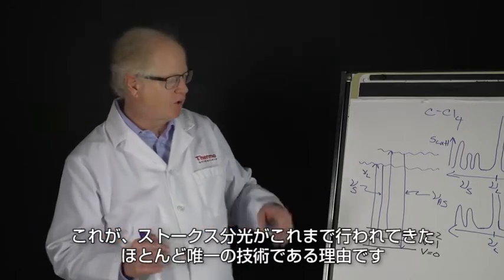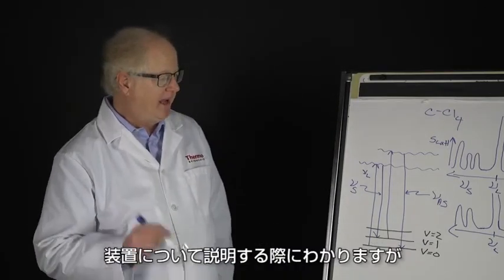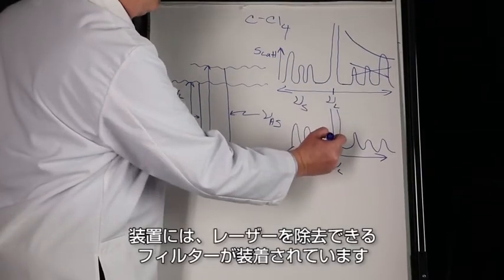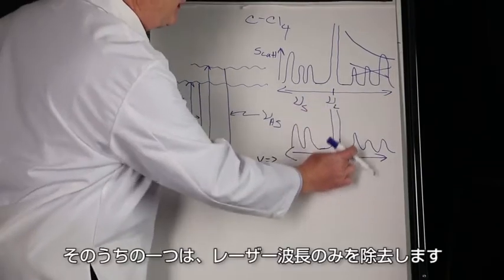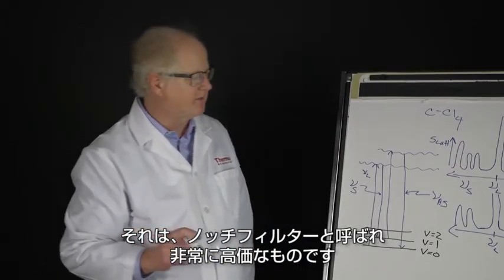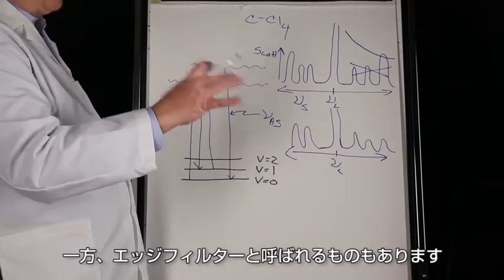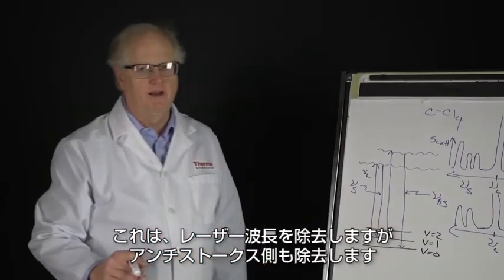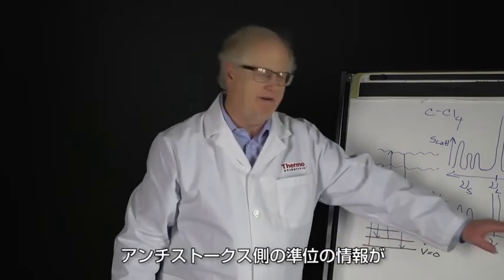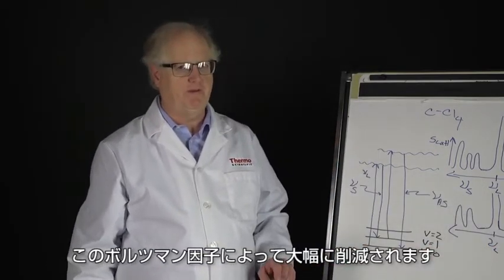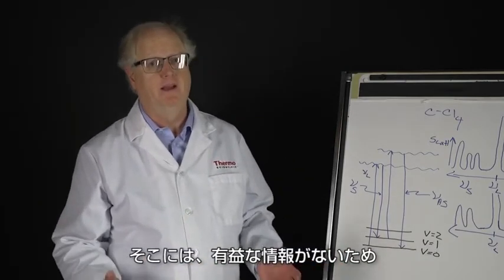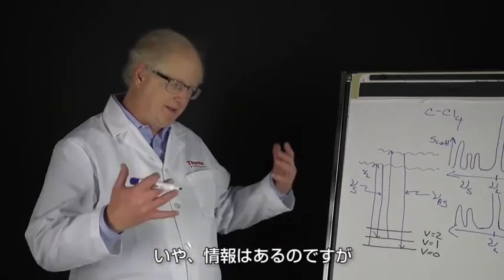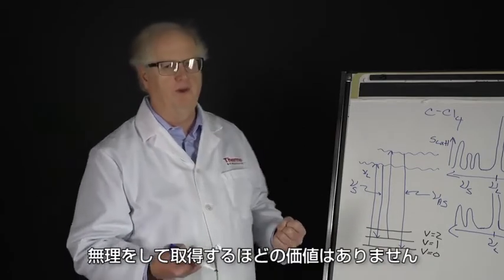So this is why Stokes spectroscopy is almost the only one ever done. As we'll see later when we talk about the instrumentation, there are filters which allow us to eliminate the laser, and there are mainly two kinds. One of them eliminates just the laser—that's called a notch filter, and it's quite expensive. On the other hand, there's something called a bandpass filter which would eliminate it but also eliminates the anti-Stokes side. Those filters are a lot cheaper. And because the level of information on the anti-Stokes side is so much reduced by this Boltzmann factor, those are the filters many vendors will choose to use because there's not useful information. Well, the information is there—I'm just saying the intensity is so much lower that it's not worth the fight to get it.